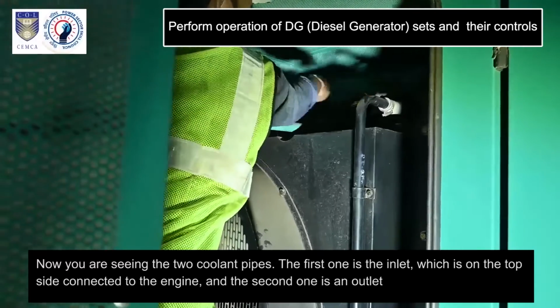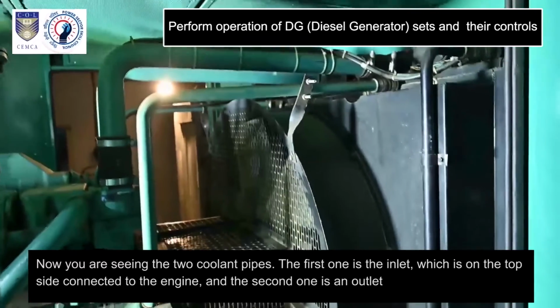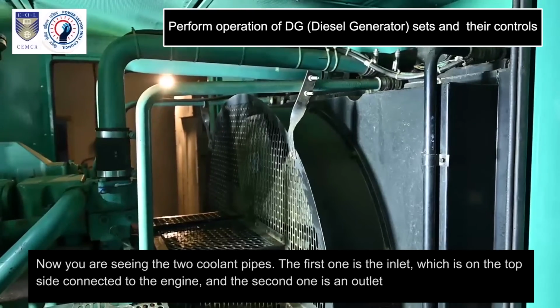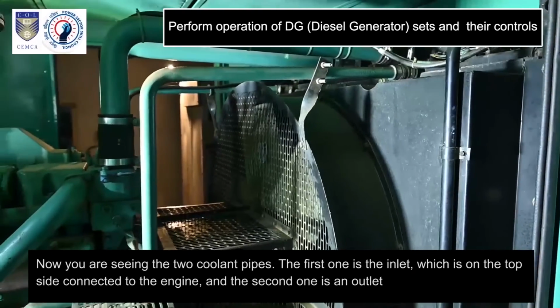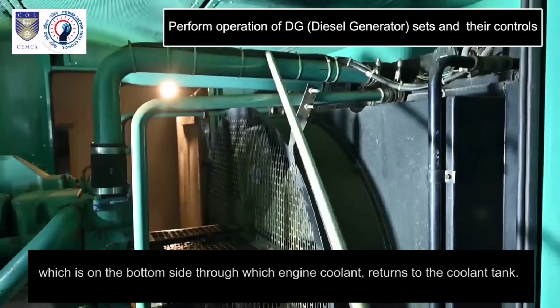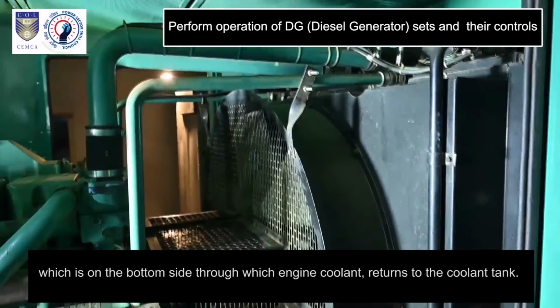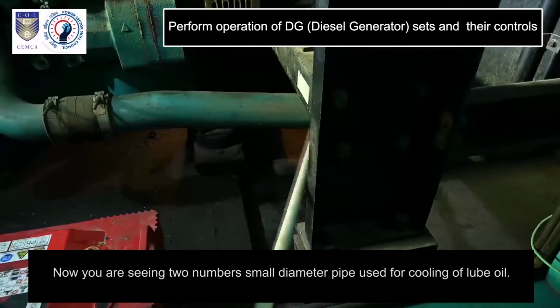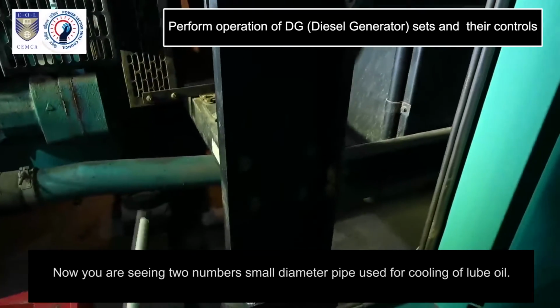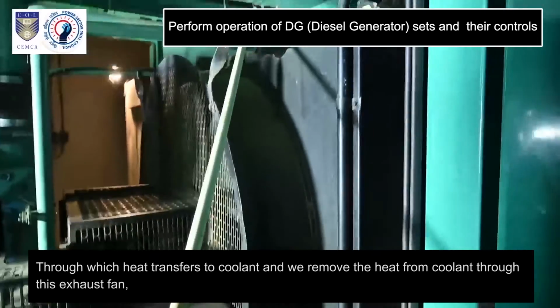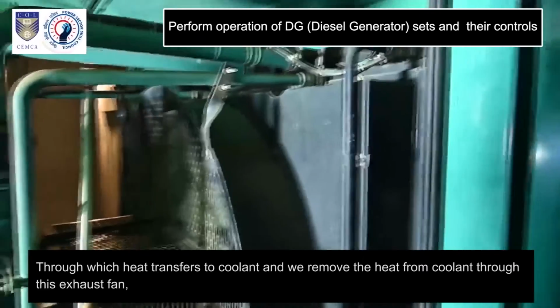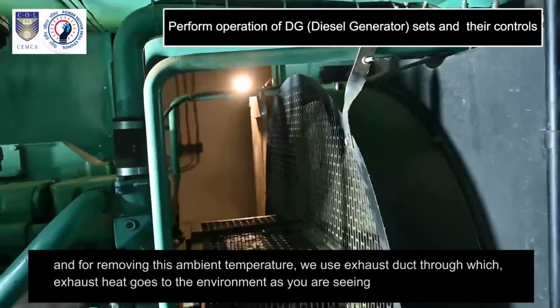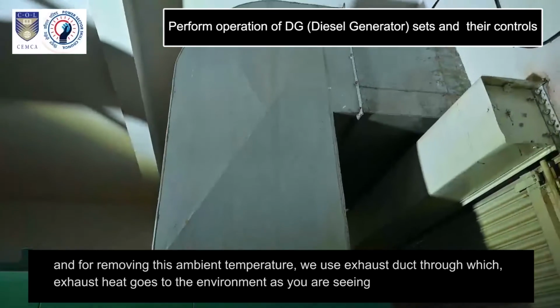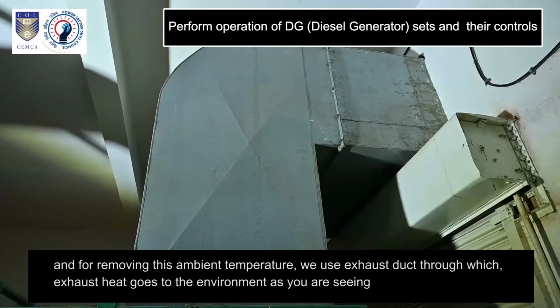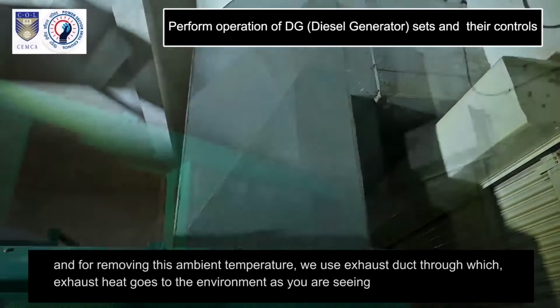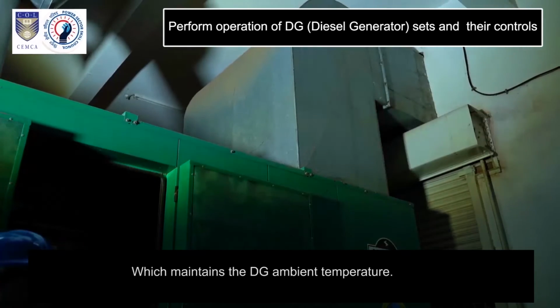Now you are seeing the exhaust fan used for dissipating heat as well as cooling of lube oil. Now you are seeing the 2 coolant pipes. The first one is the inlet, which is on the top side connected to the engine, and the second one is an outlet, which is on the bottom side, through which engine coolant returns to the coolant tank. Now you are seeing 2 small diameter pipes used for cooling of lube oil, through which heat transfers to the coolant, and we remove the heat from the coolant through this exhaust fan. And for removing this ambient heat, we use an exhaust duct through which exhaust heat goes to the environment, as you are seeing, which maintains the DG ambient temperature.